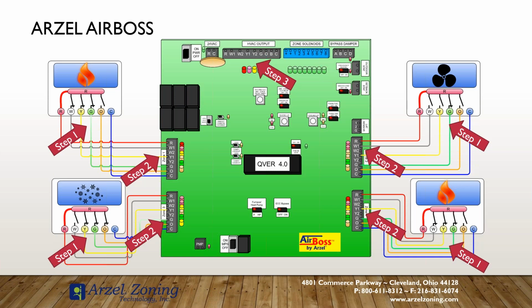And in this case, WYG is a call for heat pump with backup heat from the thermostat. YGO is a call for cooling because the O is energized. So with all the Arzel panels, you can never energize from the thermostat O and W at the same time. That would be an illegal call. So that O terminal is what determines whether it's heating or cooling. And if it's a heat pump application, O is open, it's a heating call. If it's a heat pump application, O is closed, it's a cooling call. And you can never energize O and W at the same time coming from the thermostat, because the panel will view that as an illegal call. Does that make sense, Robert?